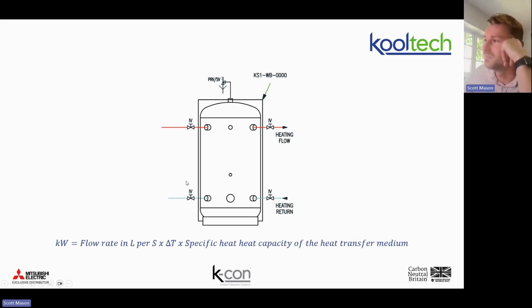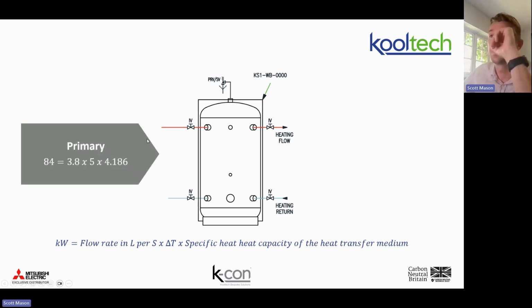That's cool. Is basically, a lot of the time, people don't want to work on a 5-degree delta T. Well, unfortunately, the heat pump kind of has to. It will work between 5 and 10, and that's fine. But if you design at 10 and it gets to site and it's 11, it's off. So design at 5, and if we need to press the up button, we can, right? Whereas what you want to do is design to 5, primary loop, into the thermal storage vessel, 40, 35 for argument's sake, because that's our heating circuit.